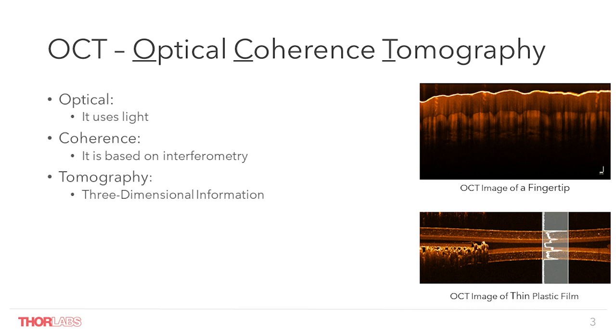First of all, what does OCT mean? It stands for optical coherence tomography. Optical — we use light. Coherence means that we are looking at interference of light waves; this principle allows us to achieve a resolution on the order of just a few microns. And tomography means that we are mapping a region in space. OCT can image 1D profiles, 2D areas, and even 3D volumes at or below the surface of a sample.